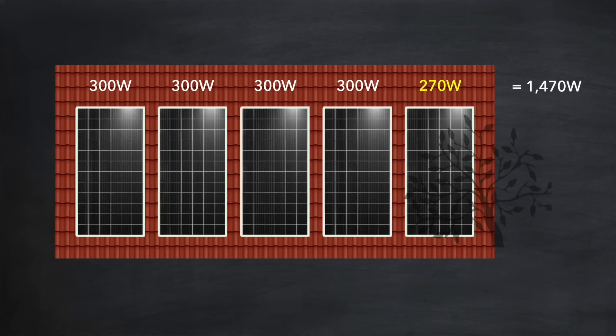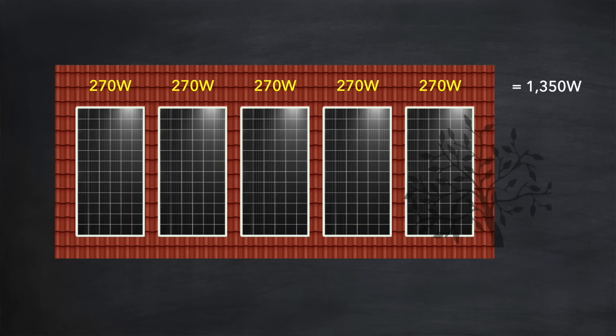But if we look at how the solar cells are connected across several panels, you can see it's just a much longer string of solar cells, and so unfortunately the same effect applies. If there is shading on even just one of those cells, it will reduce the current flowing through that cell, and therefore, if there's no capability in place to manage that shading, the current flowing through the entire string of panels. That means each panel will only be generating 270 watts, giving a total production for the array of 1350 watts. So given this scenario, how could power optimizers improve matters?